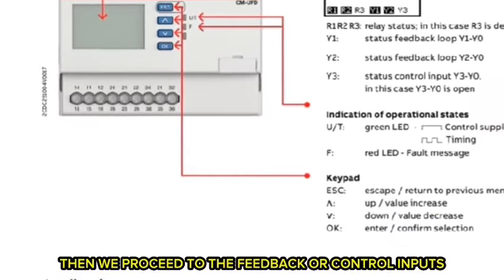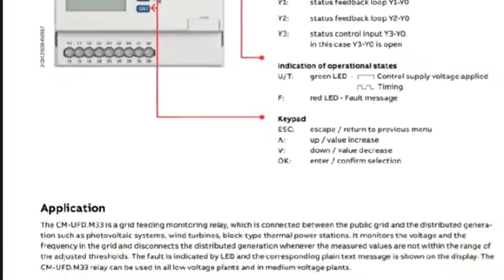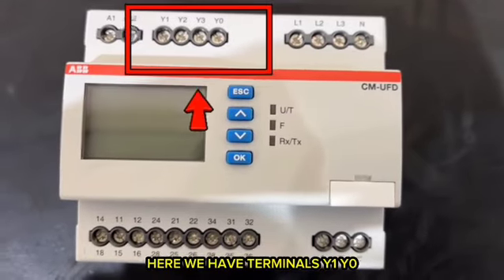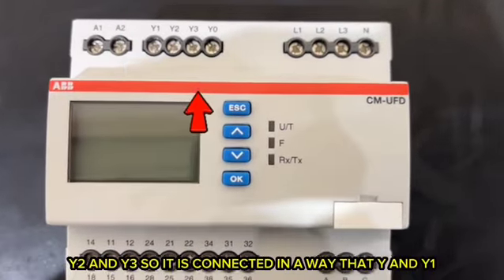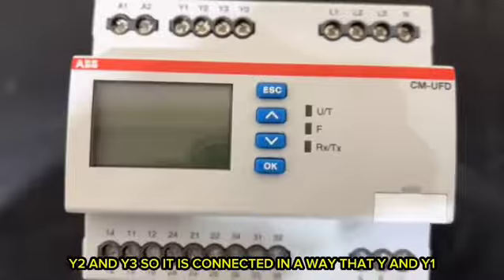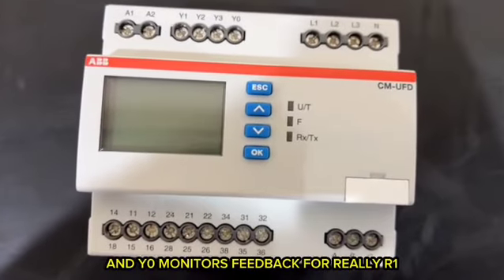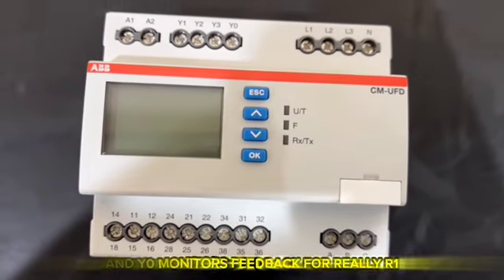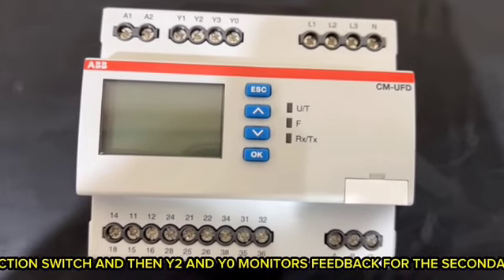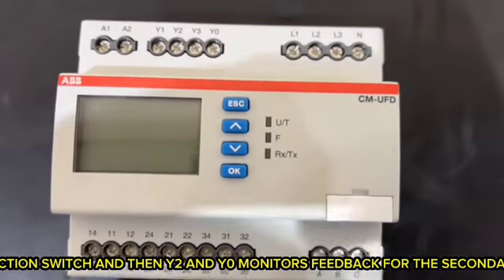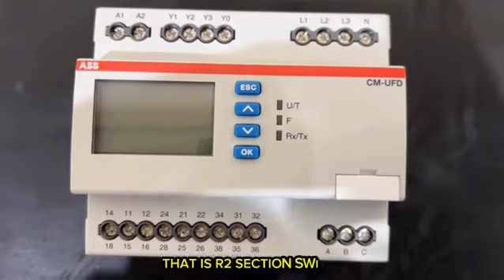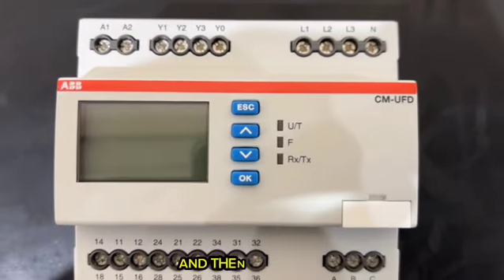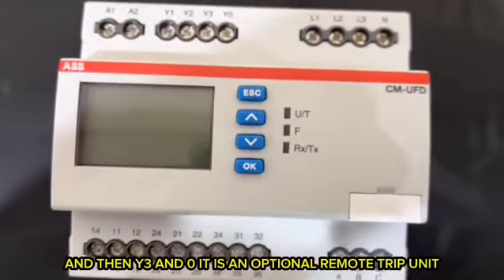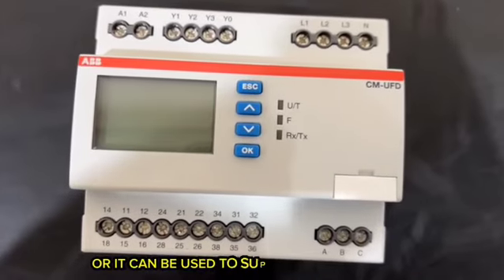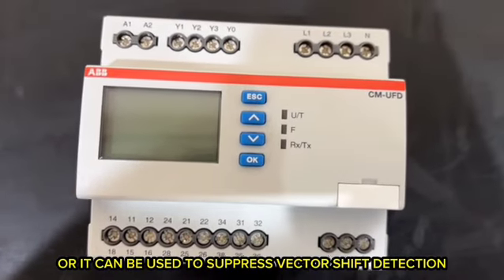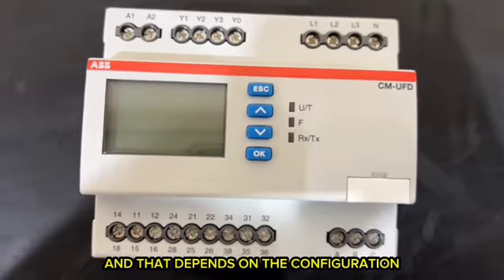Then we proceed to the feedback or control inputs. Here we have terminals Y1, Y0, Y2 and Y3. It is connected in a way that Y1 and Y0 monitor feedback for relay R1 section switch, and then Y2 and Y0 monitor feedback for the second relay, R2 section switch. And then Y3 and Y0 is an optional remote trip unit, or it can be used to suppress vector shift detection, and that depends on the configuration.